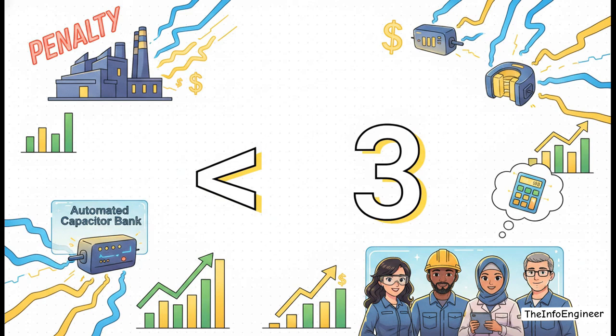Think about this number for a second. Less than 3 months. That right there is the payback period for a properly engineered automated capacitor bank. For industrial facilities getting hammered by heavy inductive loads, this isn't just a neat electrical upgrade. It is a massive financial solution that stops utility penalties completely dead in their tracks. We're going to break down the exact math on how that works in just a minute.